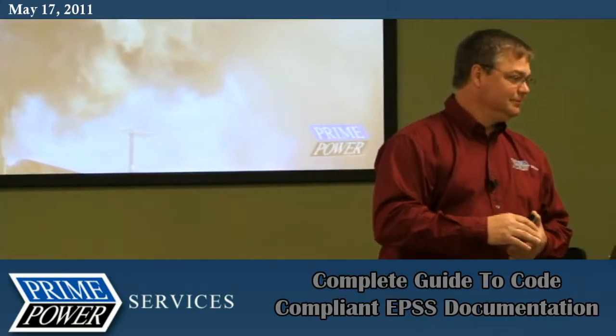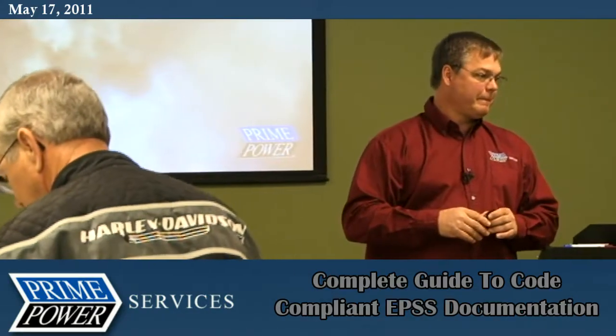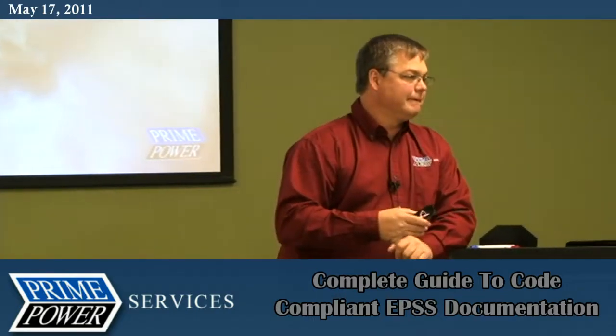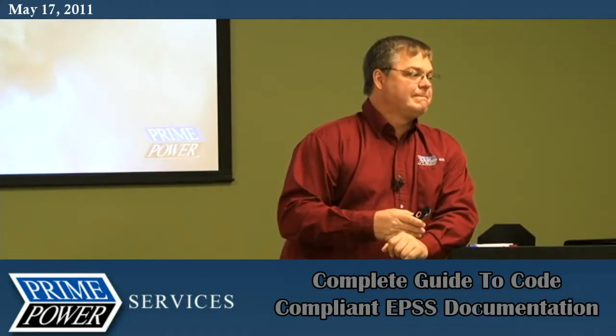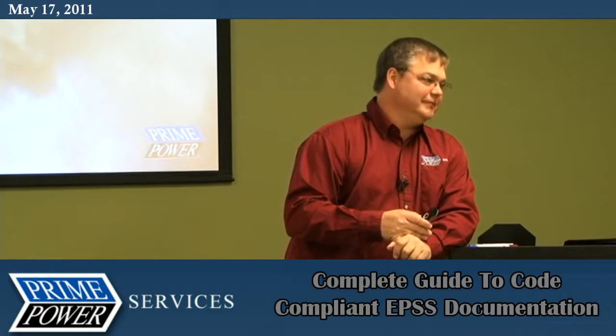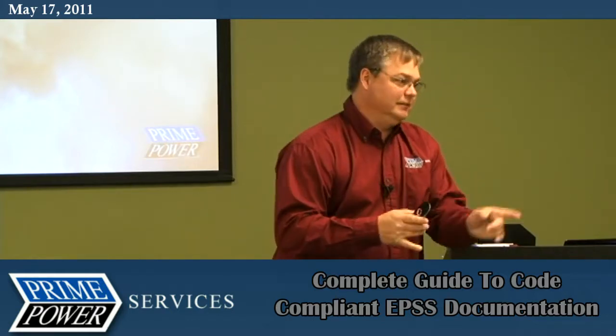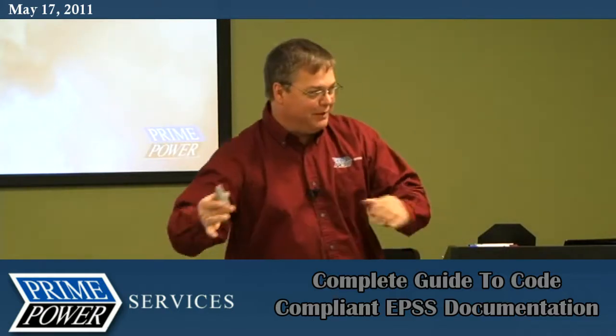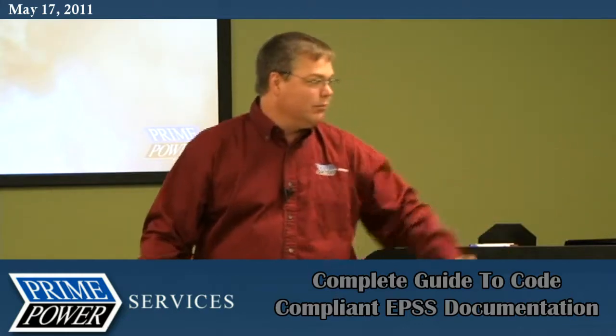Yes, sir. Terry, doesn't NFPA 110 still say that if you don't make 30%, you still have to run for 30 minutes under available building load? Yes. Monthly. Let's define monthly to weekly. And then you've got to run the load bank.